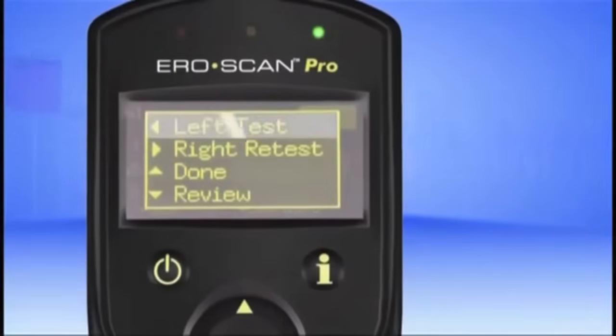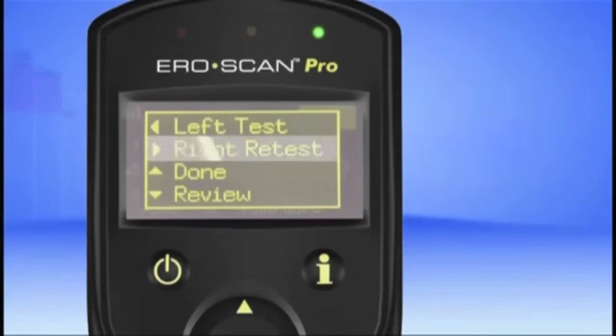Once your testing of the patient ear is complete, pressing any arrow on the navigator brings up an option menu where you have 4 choices. Starting from the top, they are left ear test. This will begin the same test protocol on the left ear. Then we have right ear retest. This will repeat the same test protocol on the right ear.